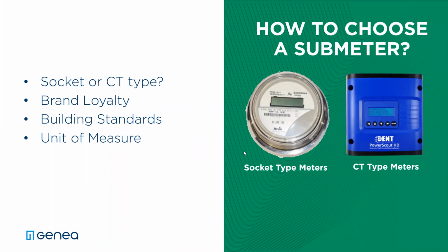The next thing to think about is unit of measure. And people say, why unit of measure, Brian? Well, when you buy things like water meters or BTU meters, they have options. Do you want it in gallons, in cubic feet? Do you want it in BTUs? Do you want it in tons? You'd be quite surprised how often somebody will read a meter and they'll read the number on the meter, but not the unit of measure. And all of a sudden, somebody swapped out a water meter head, and instead of it being in gallons, it's now in cubic feet, and we can't work out why the consumption rate has changed. So stick to the same thing - not a lot of reason to change unless you really have to.